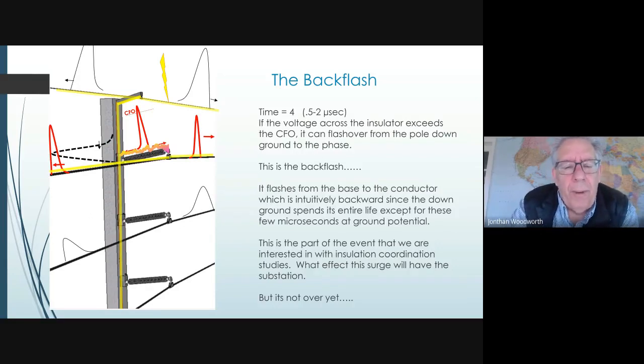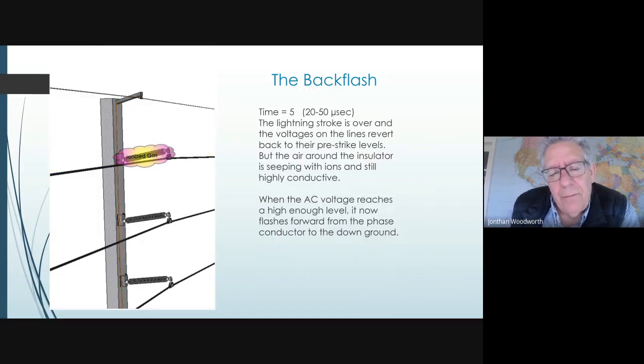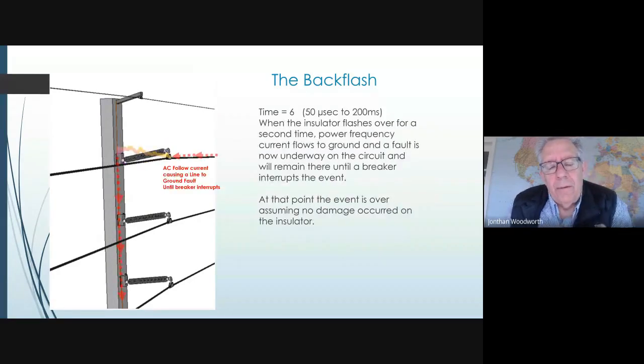So this is kind of a backwards flash. That's why it's called back flashover. The surge hits the shield, produces a voltage at the base of the insulator, flashes over to the system, and now the lightning has started the event. It's over and done in 100 microseconds, but we have a gas envelope around the insulator, and now the AC kicks back in from the other direction, and now the breaker has to operate, and we have an outage on the transmission line.